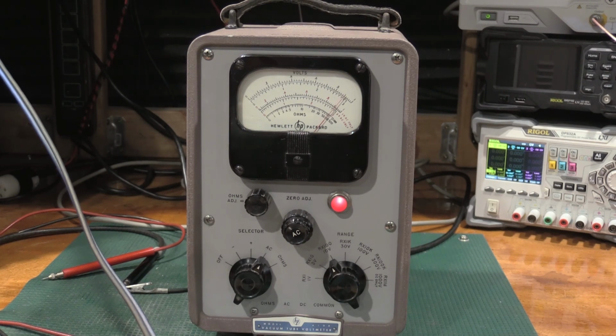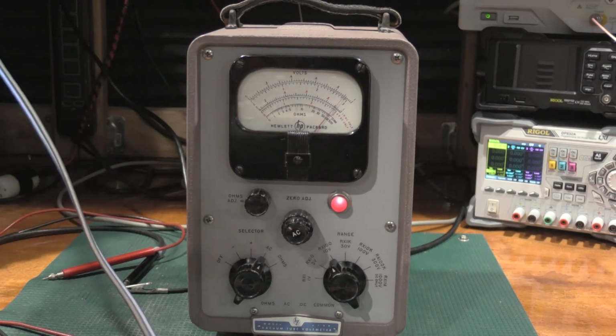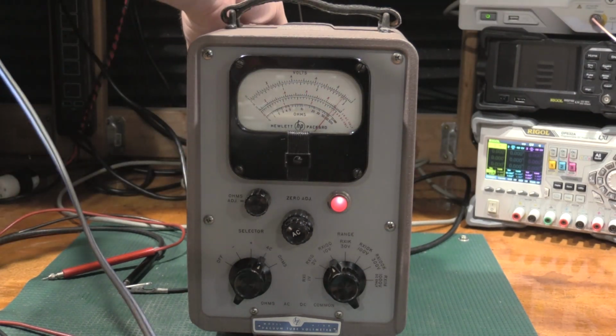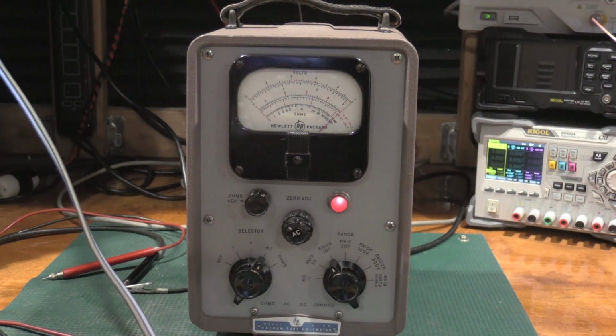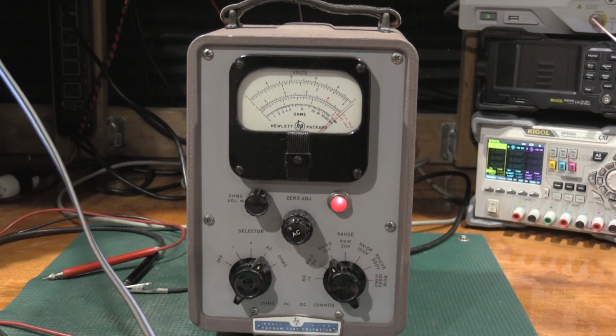10.006. Let's see if we can back it off a bit. 10 with 4 zeros. I'll take that. That won't be a problem. Now we're back to the 1 volt range, so we need to adjust for up top. So this actually needs to come up to right about there. Again, same procedure. Calibrating the meter straight on, and then we'll move to the 30 volt range.